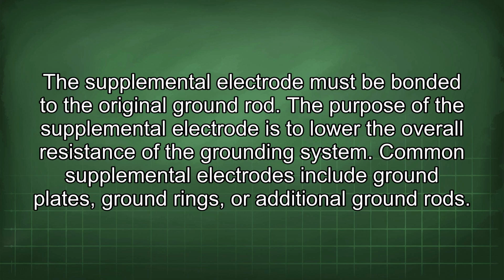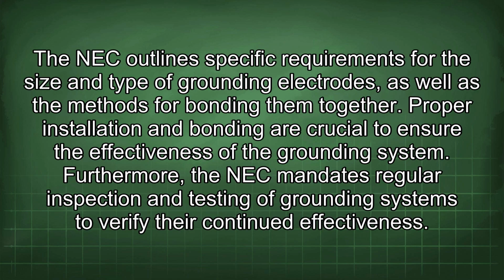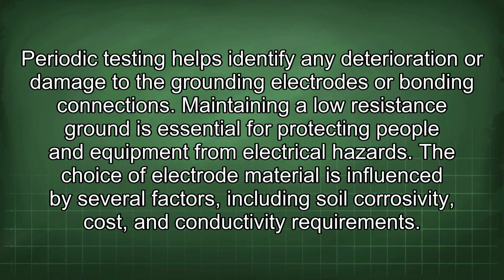Common supplemental electrodes include ground plates, ground rings, or additional ground rods. The NEC outlines specific requirements for the size and type of grounding electrodes, as well as the methods for bonding them together. Proper installation and bonding are crucial to ensure the effectiveness of the grounding system. Furthermore, the NEC mandates regular inspection and testing of grounding systems to verify their continued effectiveness. Periodic testing helps identify any deterioration or damage to the grounding electrodes or bonding connections. Maintaining a low-resistance ground is essential for protecting people and equipment from electrical hazards.